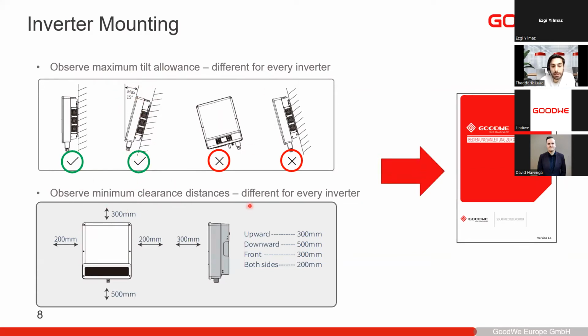This, as well as the minimum clearance distances, is very important because it assures that the cooling of the inverter is working properly. So please also check the manual for the clearance distances to the sides and to the top and bottom. This depends on the inverter model because some have the fans horizontally and some have them vertically. So please make sure that you have the correct clearance distances to also optimize the performance of the inverter and make sure that it works as it should.